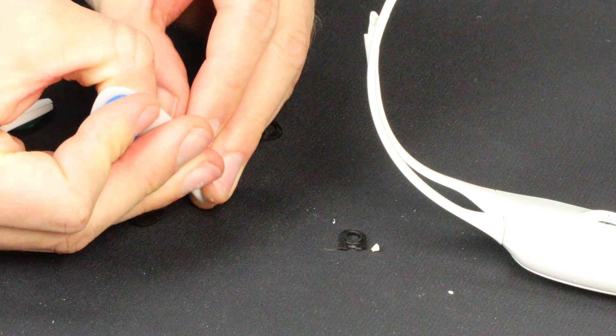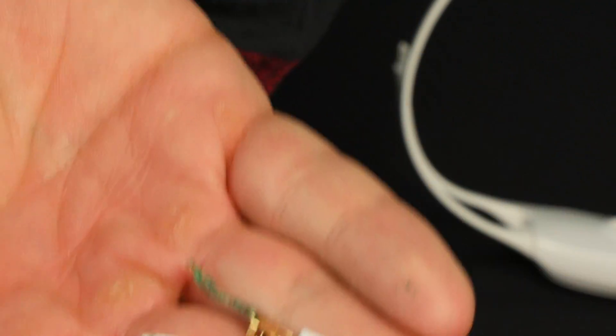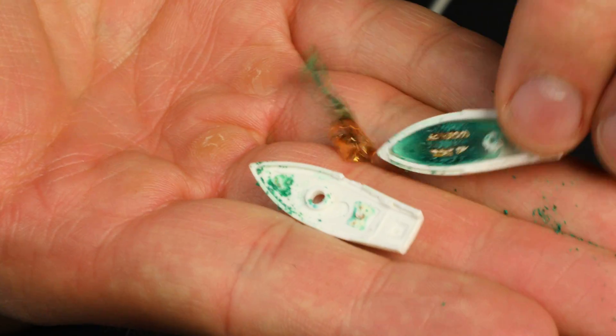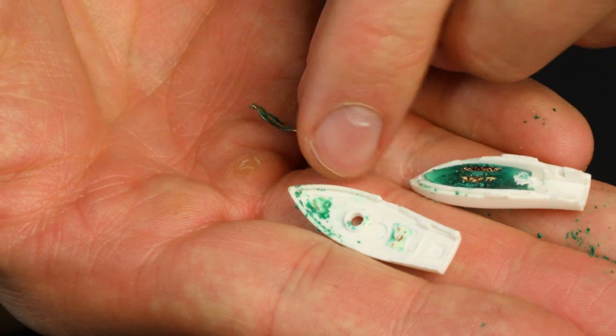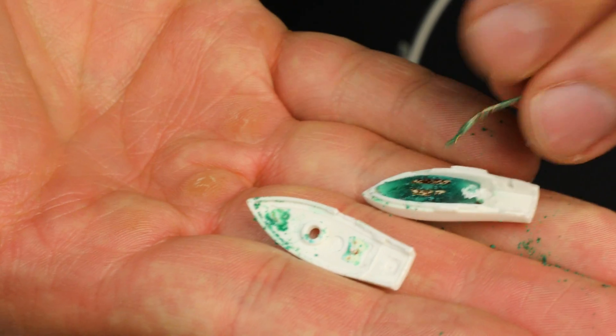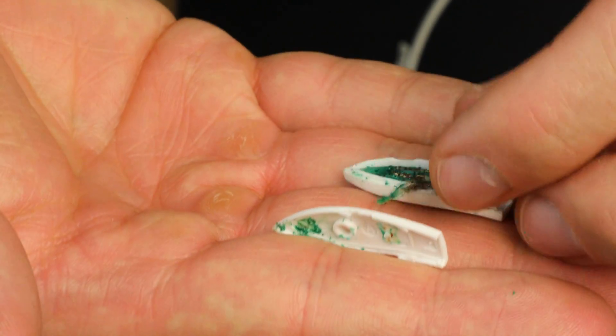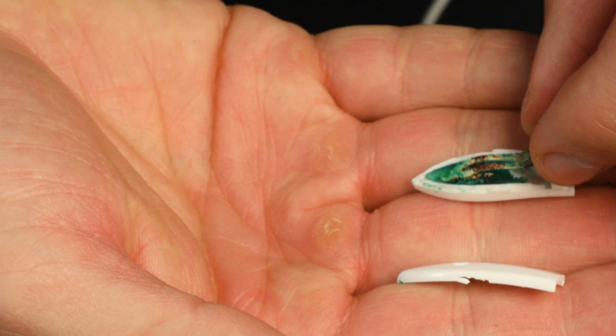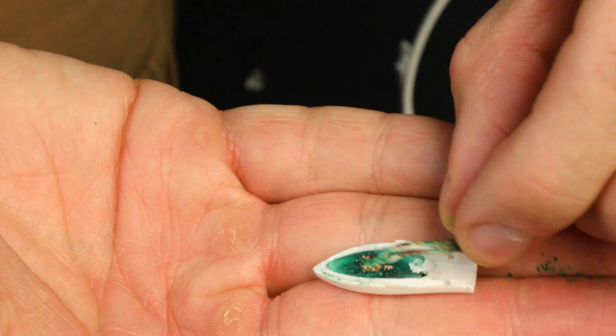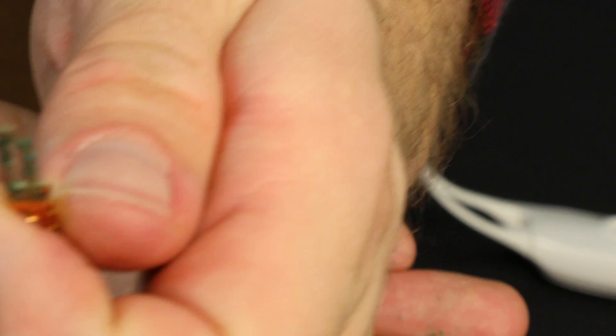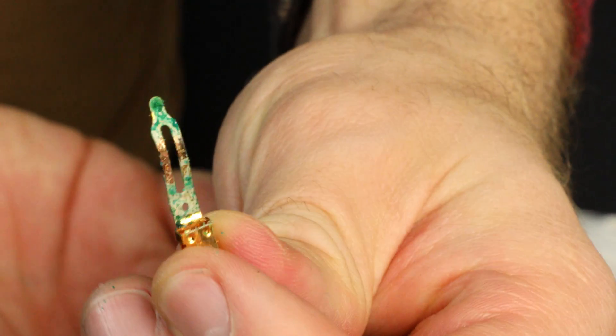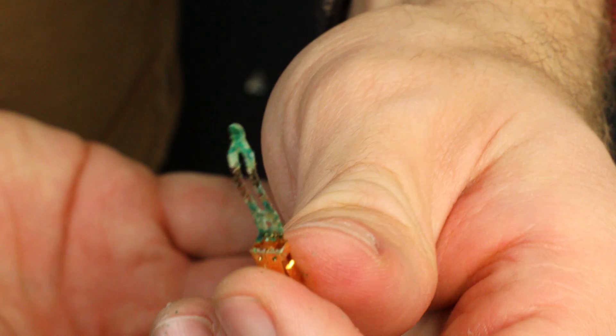Once I got the sensor open, it got really interesting. You can see the green stuff, the polymer that's part of the sensor picking up the brain waves, has really lost all of its moisture over time and is now just flaky without any sponginess to it. You can see the copper metal piece part of the sensor has some wear and tear on it as well. It was a little bit oxidized and it left behind some copper on the dry polymer gel of the sensor.